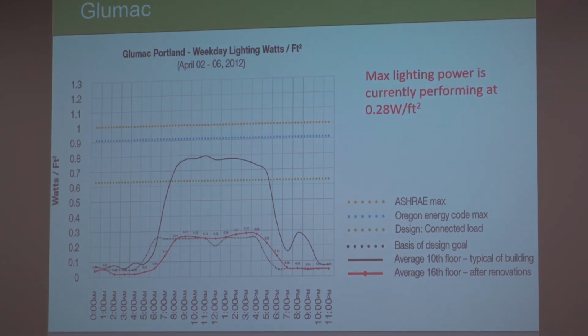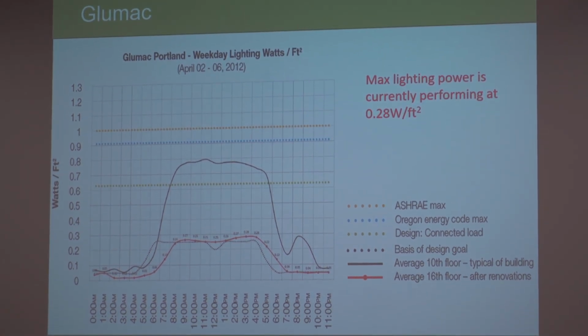So this yellow line is the ASHRAE maximum watts per square foot of lighting power that was required in the Oregon code, and that's about 1. But the Oregon code actually was more stringent, which was about 0.9 watts per square foot for the project. They designed the project to about 0.65 watts per square foot of design lighting power. Well below the Oregon code, well below ASHRAE. And here's the actual results where the system is actually operating.